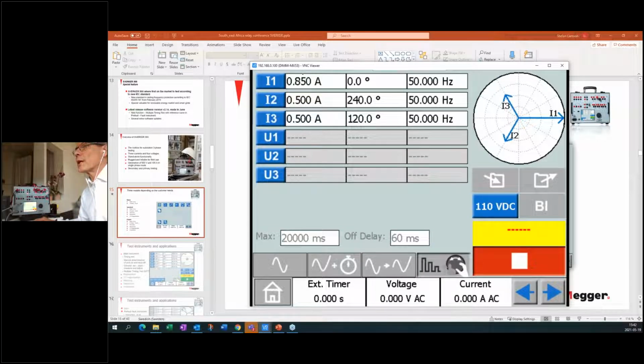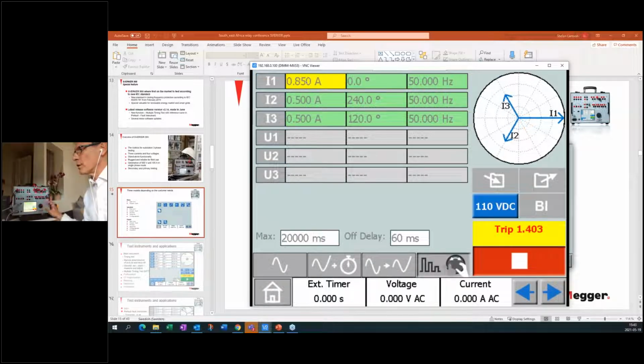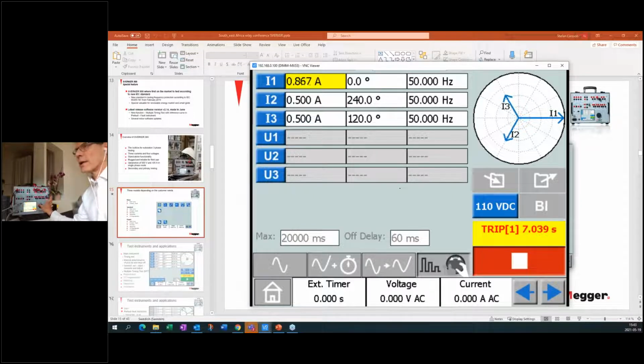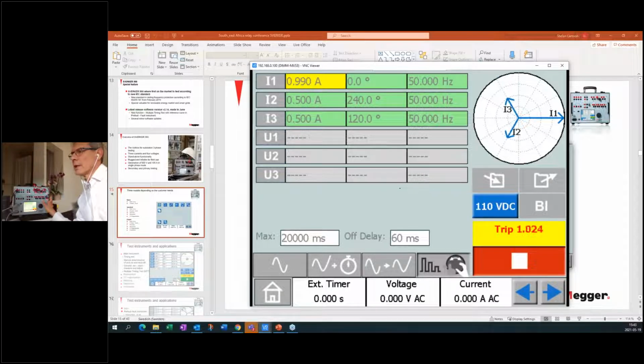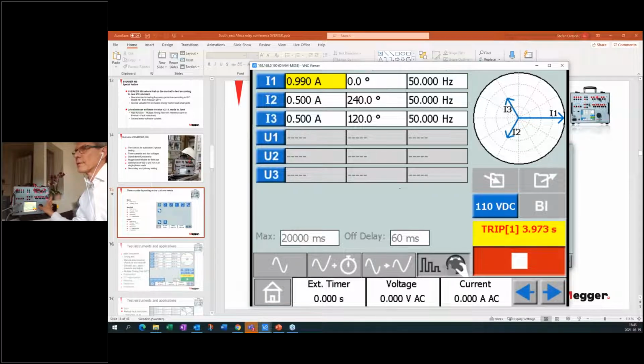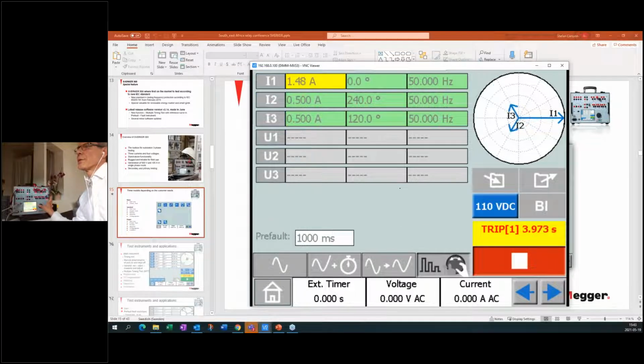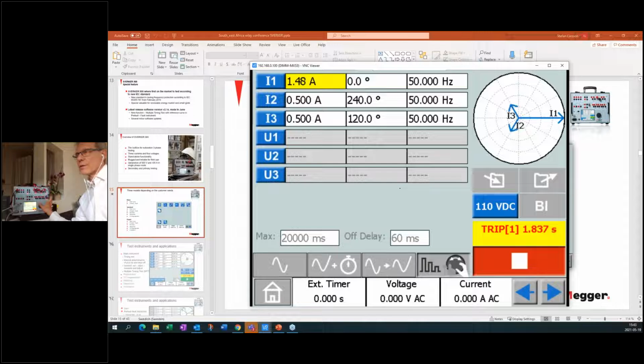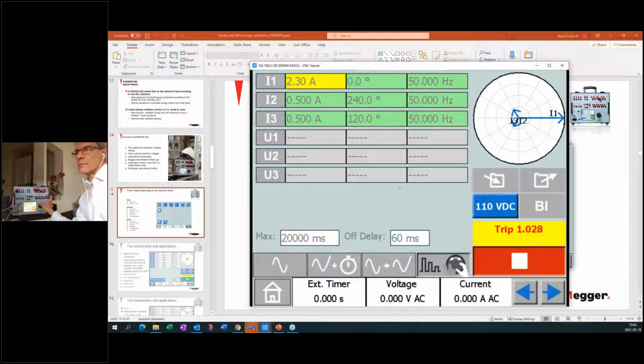And now I would like to change the current in phase number 1. So I select that one. Now I just press the knob, and you will have the time in the yellow field on the right side down on the page. So I can increase the current a little bit. So I do a new injection and I get the trip time for that. And then I continue taking some more points. And I know this has three thresholds. So the first threshold is going up to 3 amps. I take some more current levels.